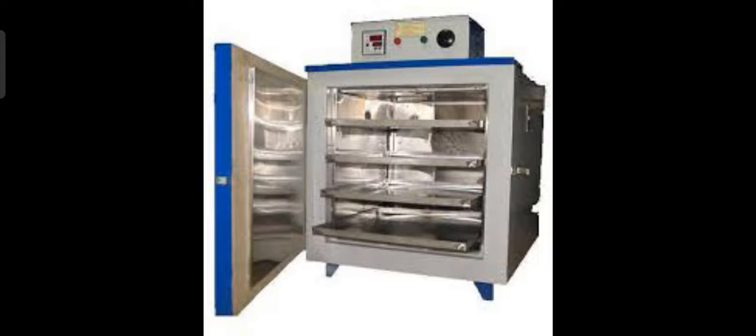What are the precautions you should take while using the hot air oven? It is necessary to check the proper temperature at which the materials are sterilized. You have to make sure that under no circumstances should the hot air oven be used to sterilize culture media, as the liquids will boil to dryness. There should be a temperature controlling device for maintaining the temperature required for sterilization. The hot air sterilizer is used for sterilizing laboratory glassware.